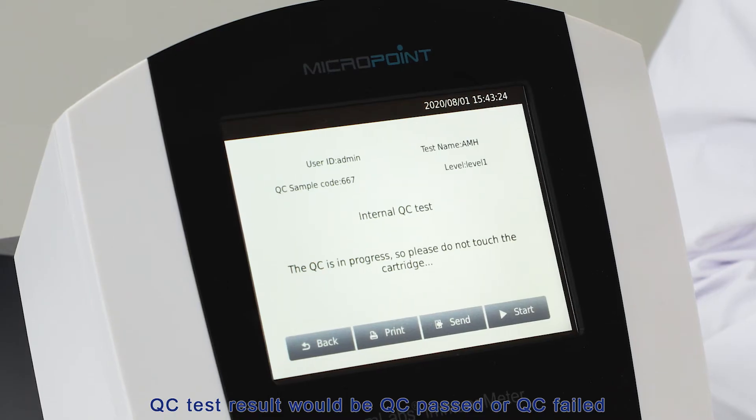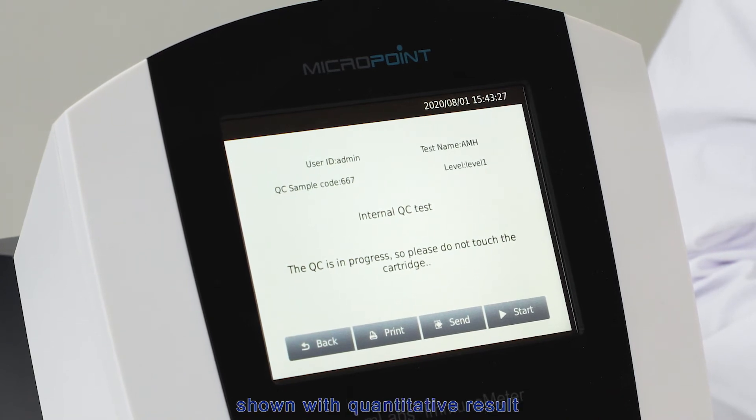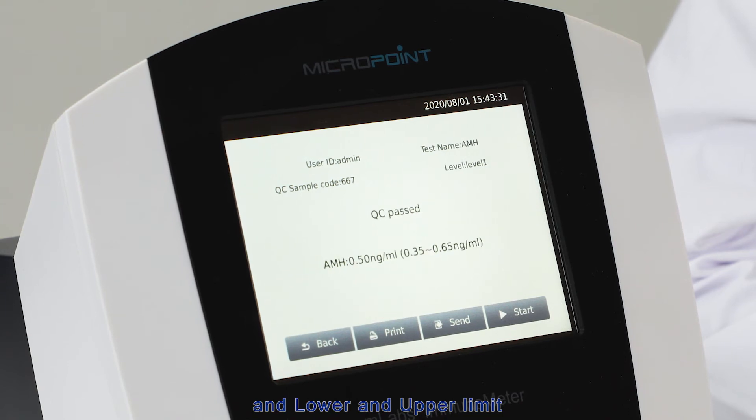The QC test result will show either QC passed or QC failed, shown with quantitative result and lower and upper limits. QC failed means the test result exceeded the limit range — you will need to repeat the QC process, paying attention to every detail of the operation. If it fails again, please contact your MicroPoint distributor for further information.